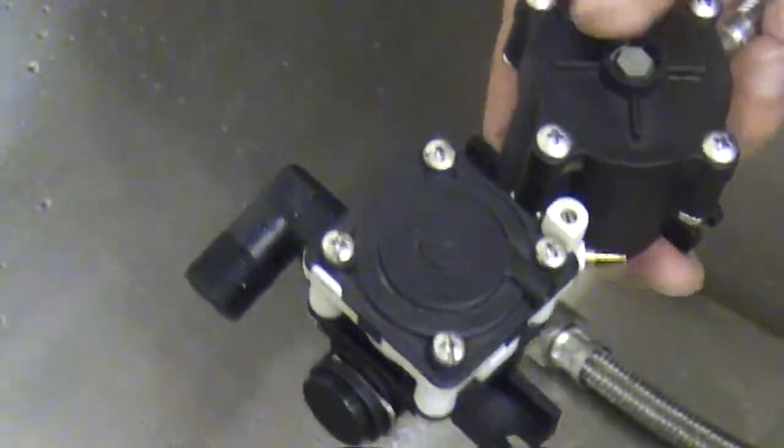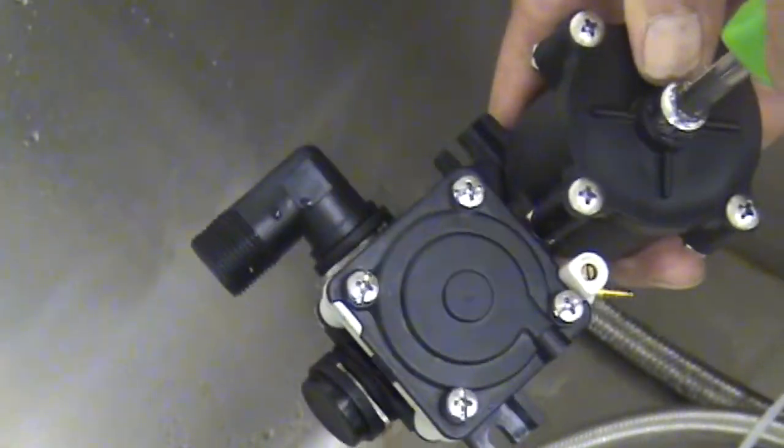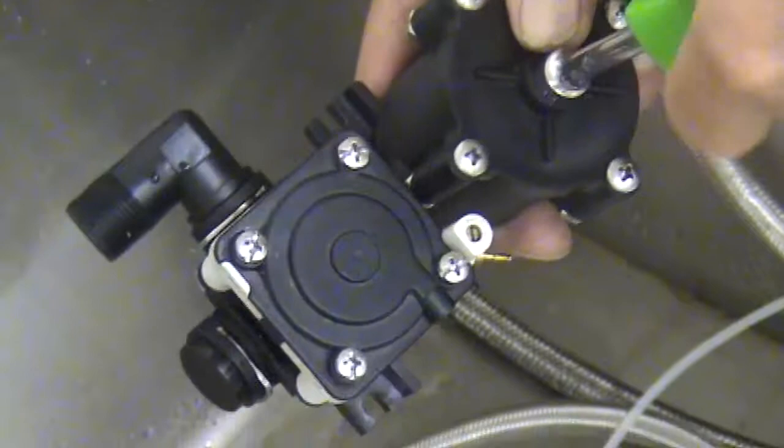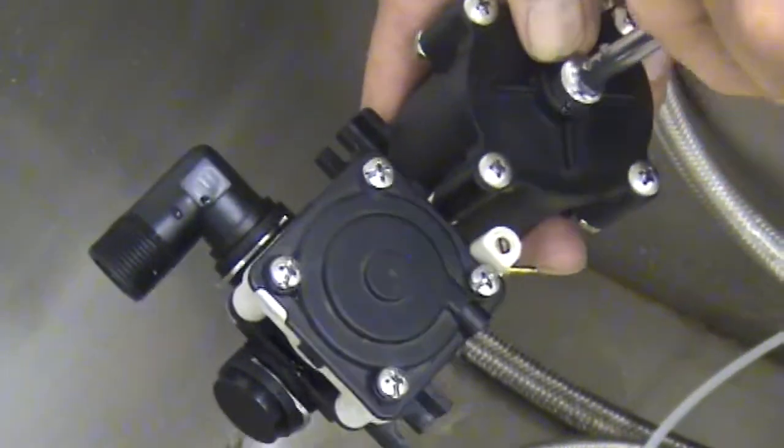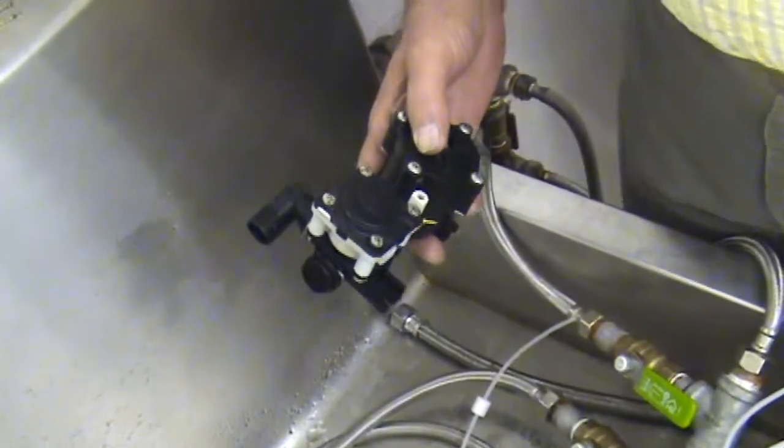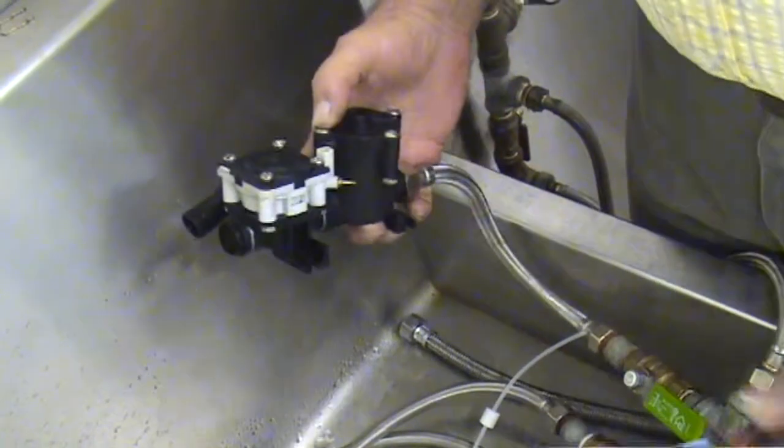However, sometimes that will not resolve your issue and the valve will keep on running, whether the tubing's connected or not. So that tells us that the problem is internal in the water chamber of the valve.